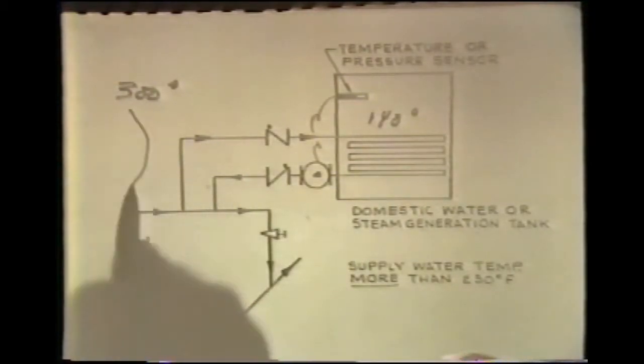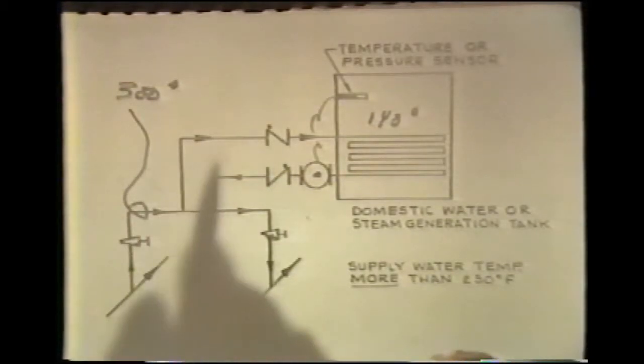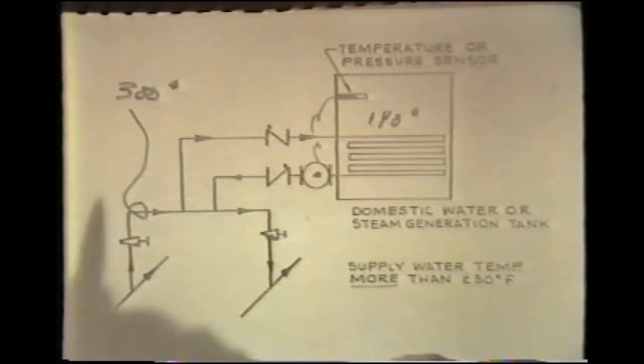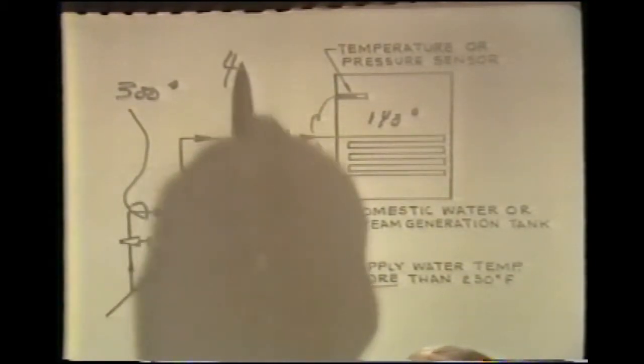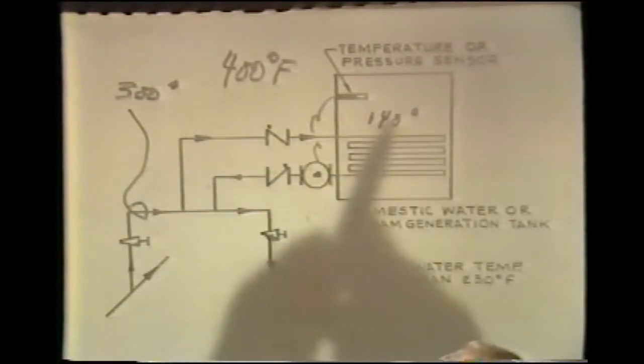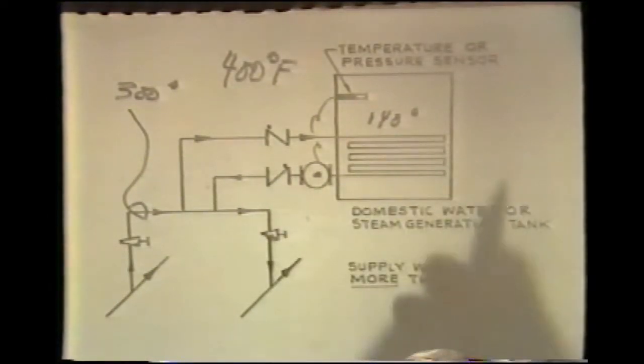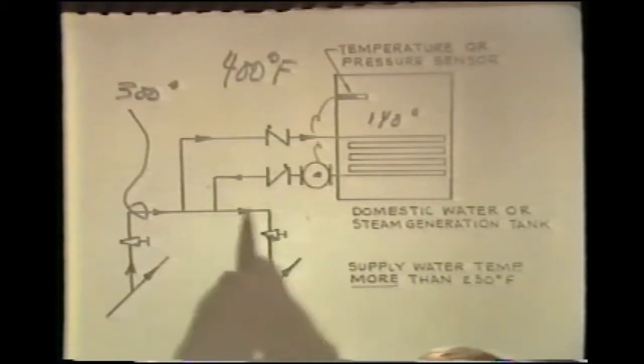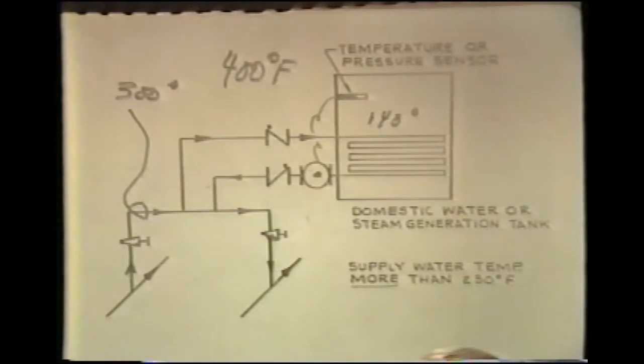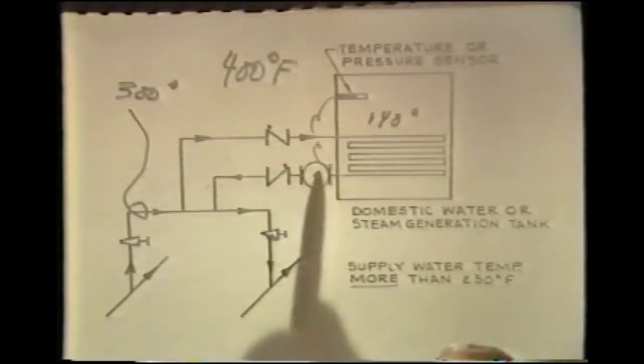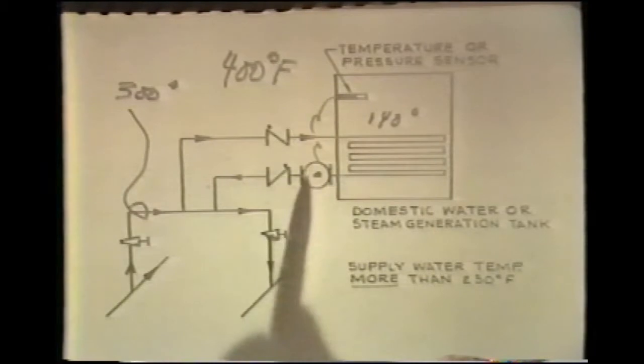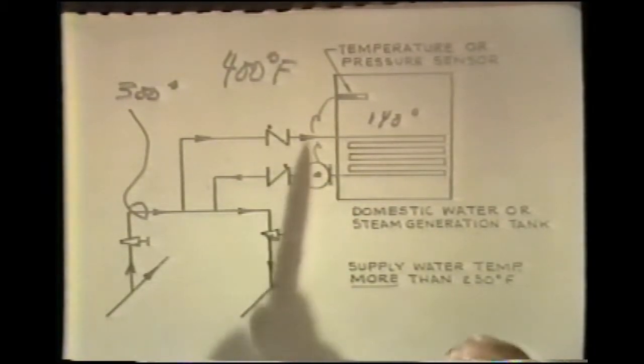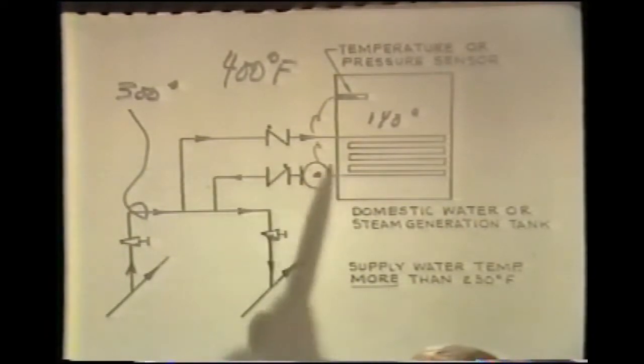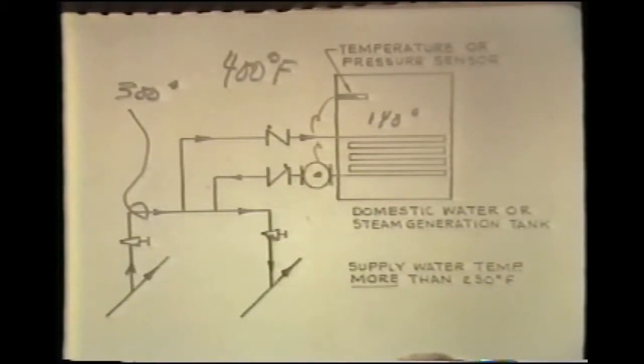And we can take a very high temperature drop across the distribution main corresponding to those temperature drops normally associated with water systems operating at 400 degrees Fahrenheit, and compete very, very closely with those types of systems in terms of reduction of flow through the primary distribution main. There are, as stated before, many applications for the usage of single pumps in terms of primary-secondary applications, which simply can't be covered in terms of time. Let's illustrate then some of the further continuation that we had in terms of primary-secondary pumping development.